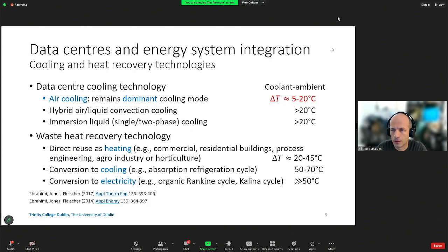The slide here just shows the current state of affairs, and the next talk by Professor Poulikakis will also, I'm sure, deal with some of these things. The dominant cooling mode at the moment for data centers is still air cooling. There's a lot of talk about liquid cooling, but for the most part, especially in Ireland, 99% of these data centers are air cooled. That means the delta T, the temperature difference between the coolant outlet temperature and the ambient, is very minimal, something like 5 to 20 degrees Celsius or so.